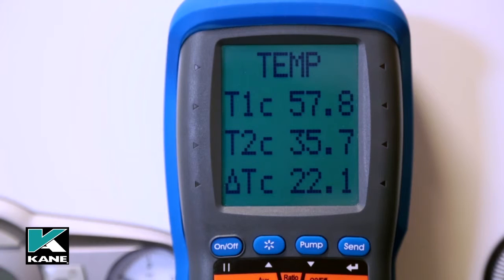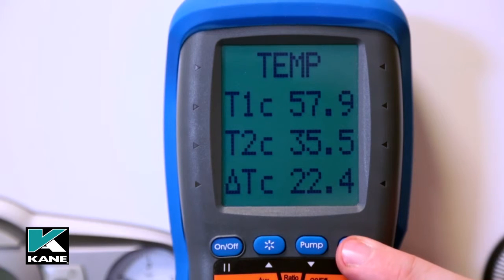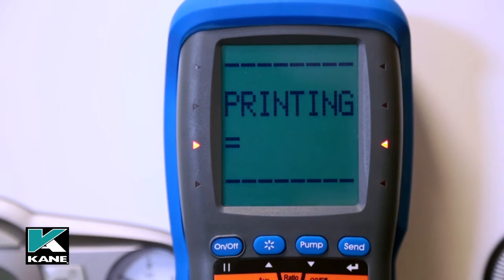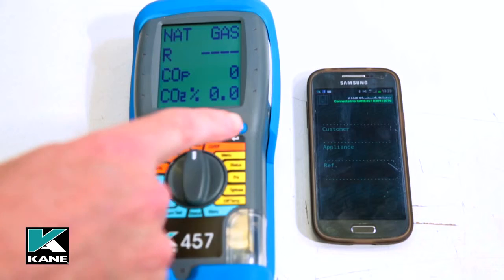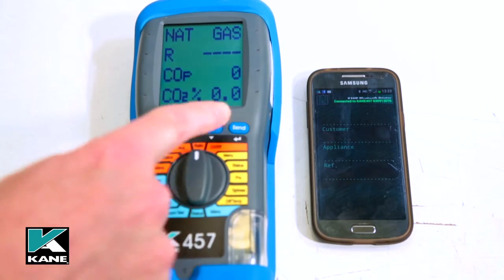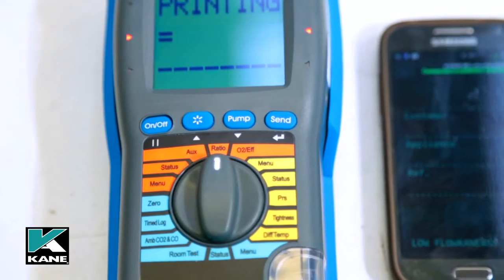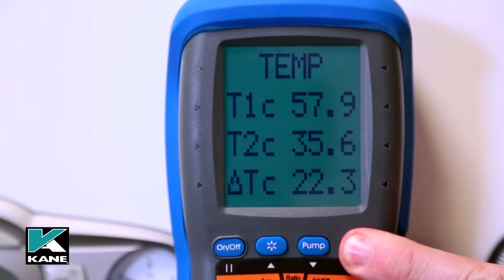The display is as follows. Use the T1 connection for the flow temperature sensor. Use the T2 connection for the return temperature sensor. Real-time temperature difference. Press Send for 1 second to do a live print of the differential temperature test. Also sends to PC and Android app if Bluetooth fitted. Hold Send for 2+ seconds to log a differential temperature report.